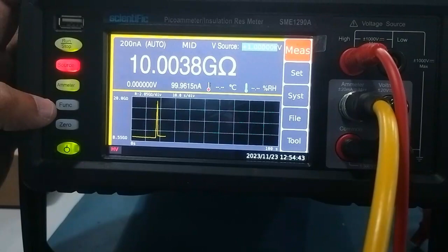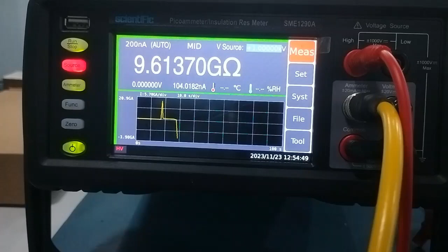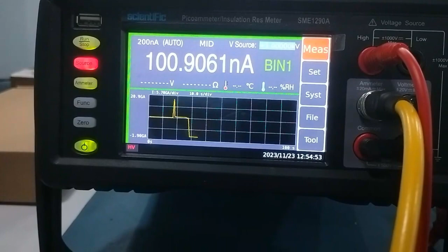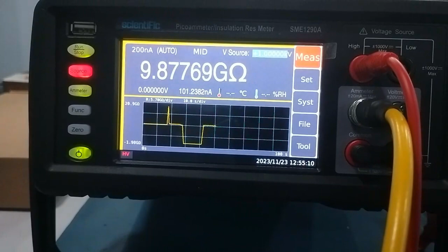If we want to see the current, we can press the function and we can select the ammeter. So this is our current range, 100 nano ampere. Again we can go to high resistance. And our resistance is coming around 9.9, 9.8. So this is how we can do the high resistance measurement by using this instrument.